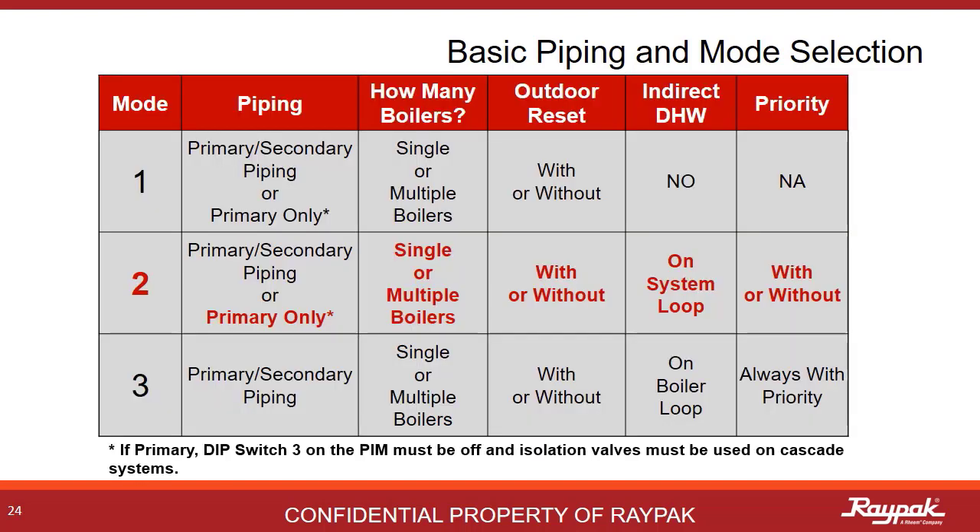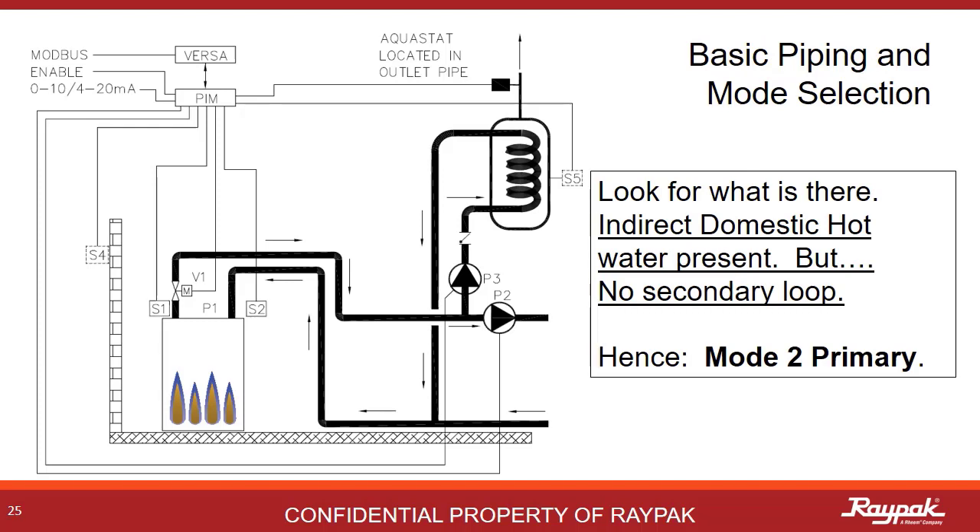The last option is mode 2 primary systems. Here there is an indirect domestic hot water tank on the system loop. For all primary systems, dip switch number 3 on the PIM must be off — this tells the Versa that it is plumbed primary. This is a single boiler mode 2 primary system — it's just a single loop with an indirect domestic hot water system on the loop. That motorized isolation valve might be required depending upon your local codes.